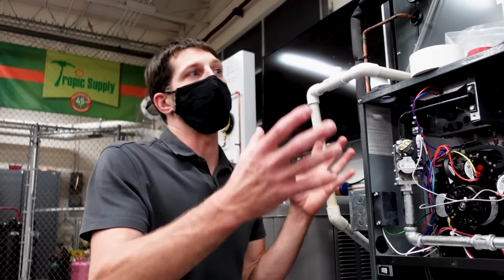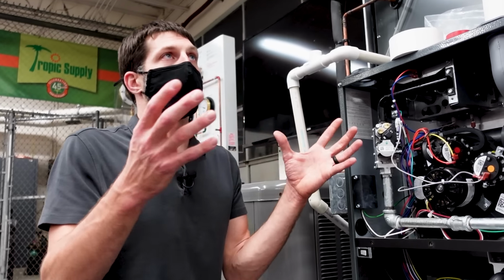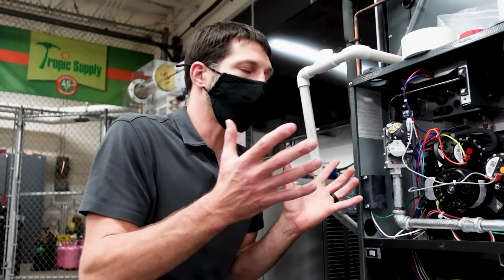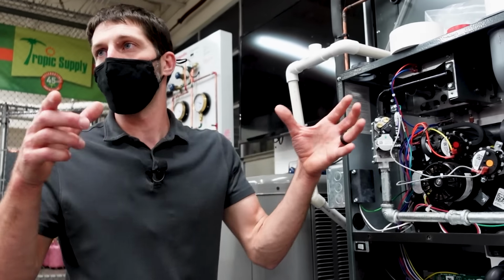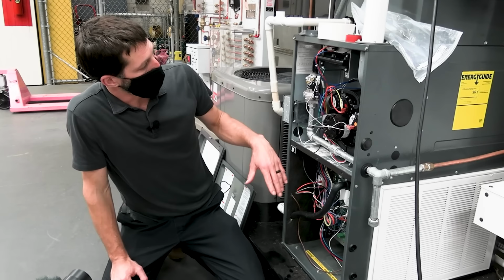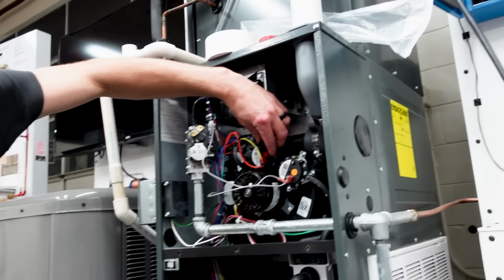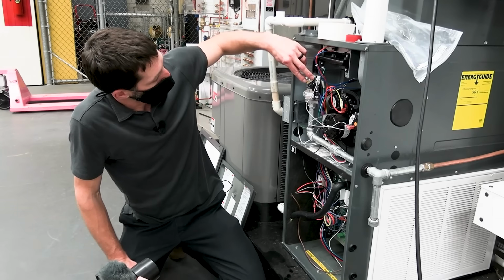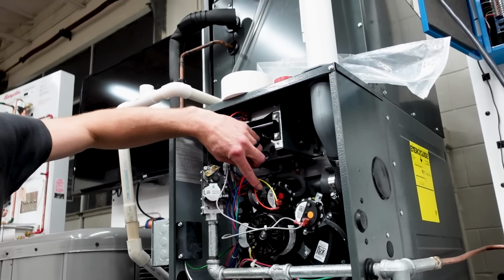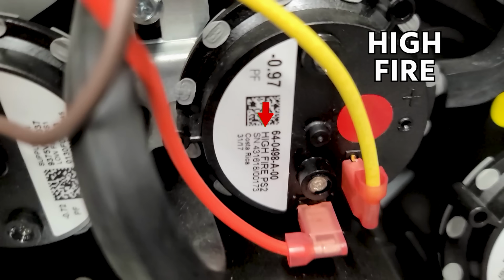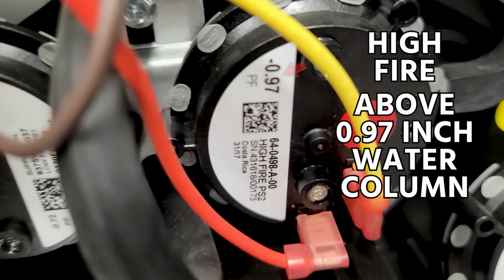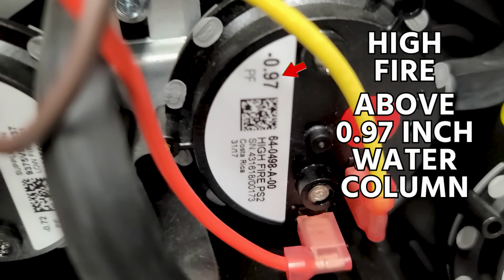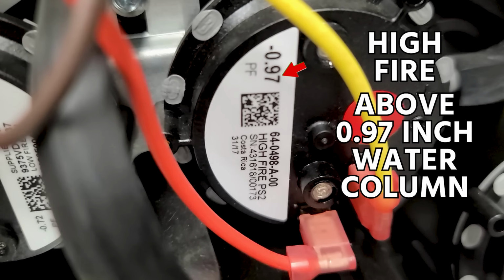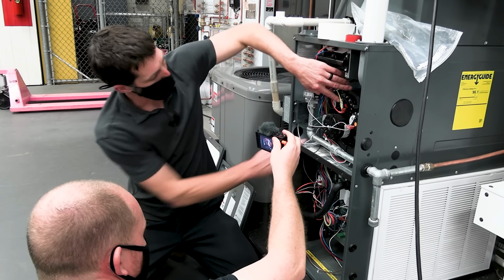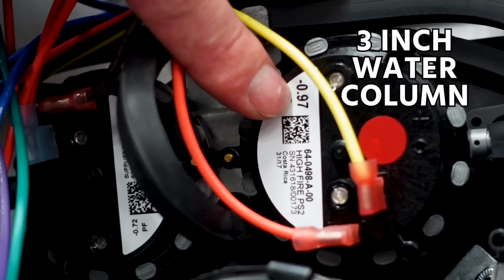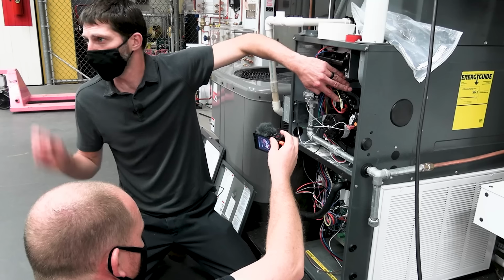So you can't just say all B vent is that way, because there's newer types of B vent that you could use even on a wood stove, and it's much higher temperature. You have to have more clearance to the combustibles. Anyway, getting back to this, you have 3 pressure switches here, here, and here. We already said that this is a 2-speed furnace, so you have a high fire, so that's when the inducer motor is running at above 0.97 inch water column. So remember that. So right here, this inducer motor may be pulling 3-inch water column. So it's a very small amount of pressure.